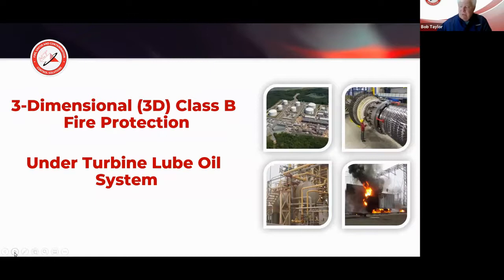When you have these types of fires, generally they become a three-dimensional fire. Like underneath the turbine, you have all kinds of piping and cable trays and structures and a lot of obstructions. And it creates that three-dimensional scenario where foams don't work well. Foams aren't designed for 2- and 3-dimensional fires. They're designed for those one-dimensional, spill type areas, and even to be contained within that.